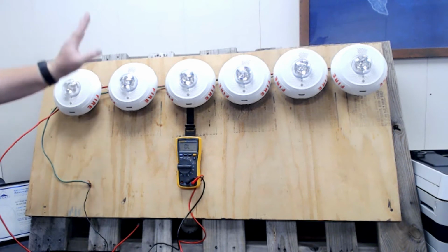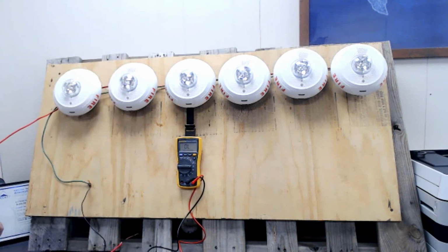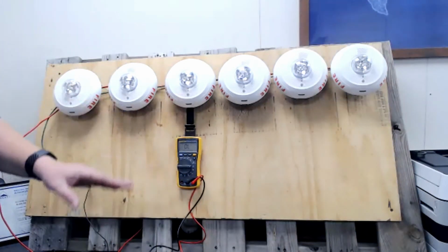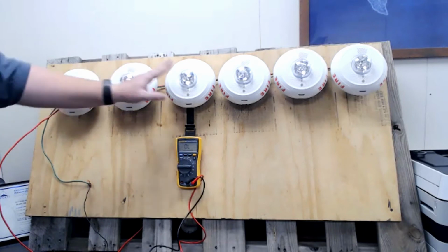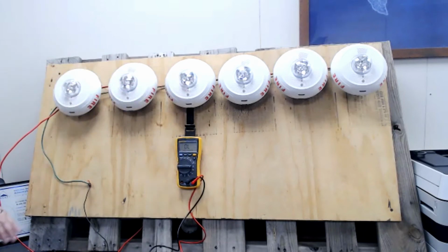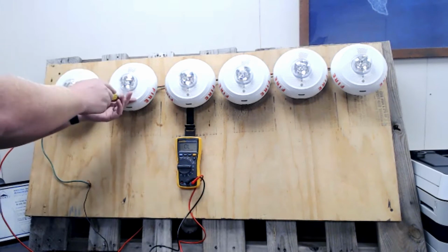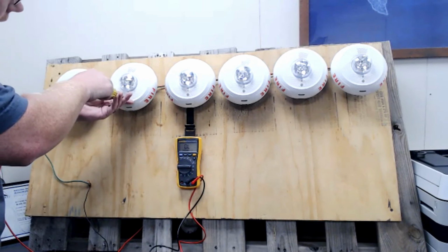I'm going to go ahead and just go to this next device here, device number 2, because when I checked it at my home run, I had greater resistance than when I checked it here. So it's most likely going to be closer to this device than it was to over here. But remember, it's always closer to where you have the least amount of resistance.